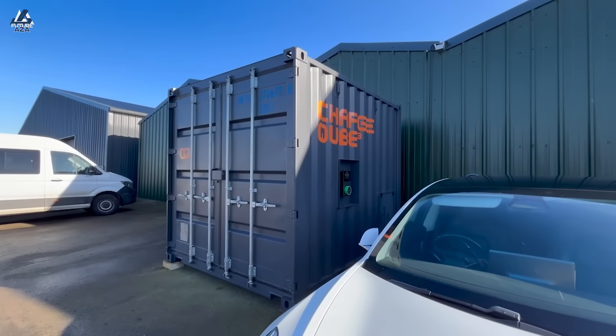It's really great especially at job sites. There will be periods where you need more power than the grid can provide, but it's not all day - it's just for an hour or two, or even a few minutes. A 10-foot ChargeCube can house up to six 75-kilowatt-hour battery packs, offering a total capacity of 450 kilowatt-hours. They also do larger 20-foot containers that can store 900 kilowatt-hours. It's using second-life EV battery packs, and they say they've got at least 85% of usable capacity that'll probably last for another 25 years. Because you've got extra packs stacked, you're not continually discharging and recharging them - it's doing it far slower, so the expected lifespan will be at least 25 years.